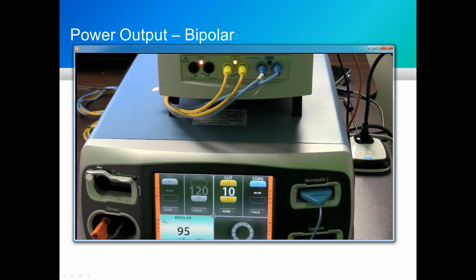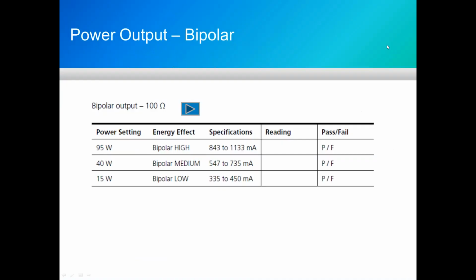Notice the yellow LED coming on right above the yellow cables. That just indicates when my contact is closing on my cut output, and that is the cable going to the foot switch adapters that we put in place on the back end of the FT10. So there's the test that we just did, and again, everything is operating to our satisfaction.